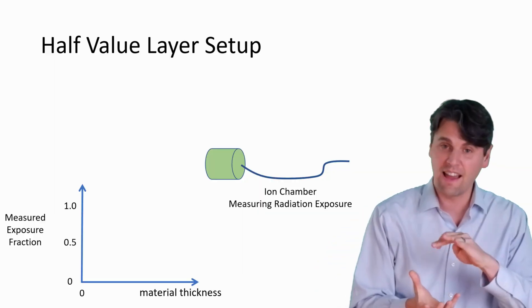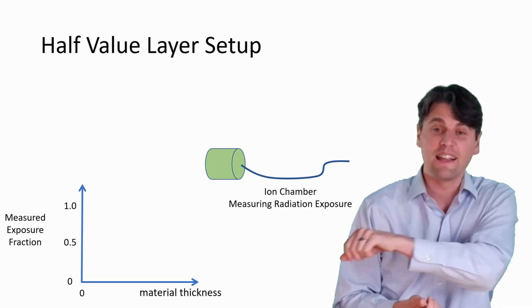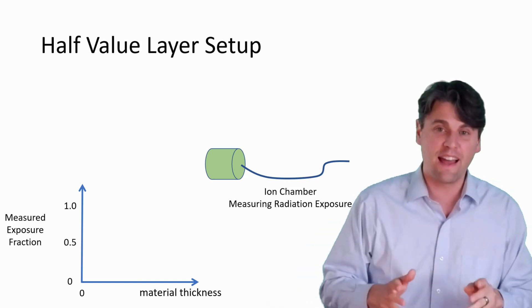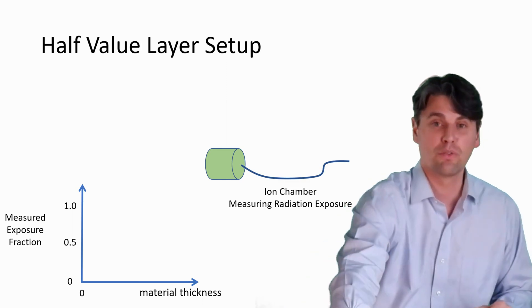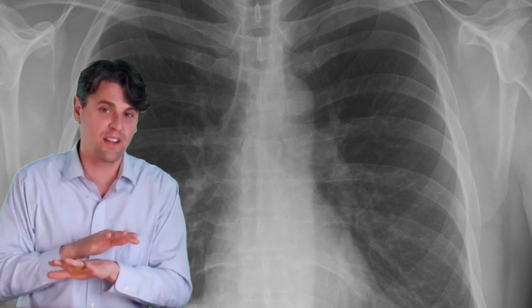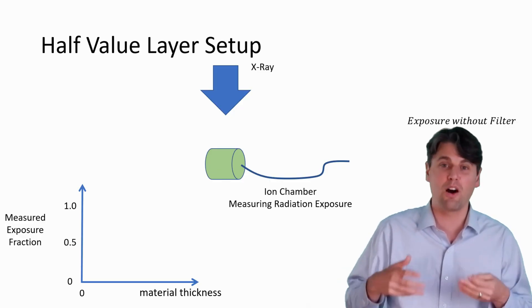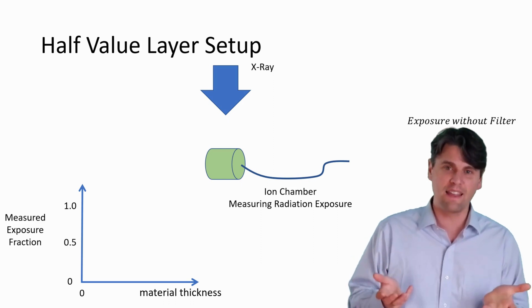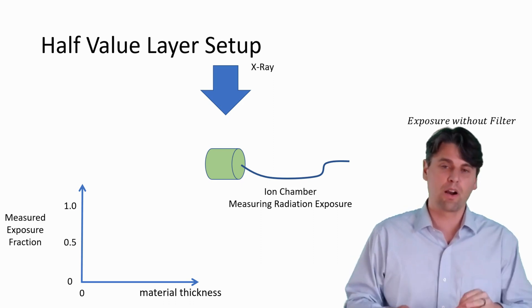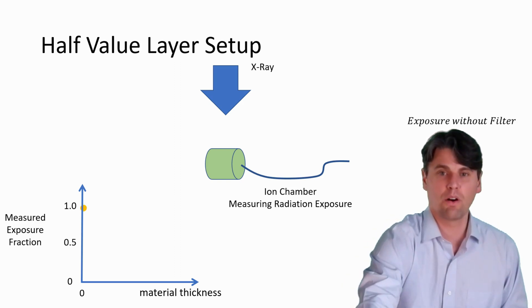Those electrons are going to get amplified, the signal is going to come out, and that signal is going to be proportional to the exposure. Next off, we do that with no filtration in the beam. It gives us our exposure without filtration. We're going to use that for what we call normalize or divide the other data by this number because this is our baseline value for the exposure with no filtration.